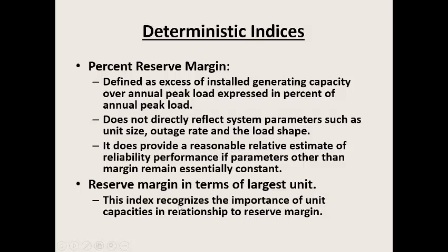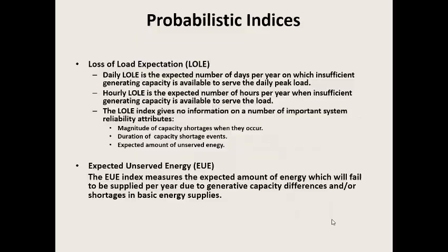This recognizes the importance of the unit capacities in relationship to the reserve margin, because the units which have larger capacities, when they fail, are going to have a more dramatic effect on the reliability than the smaller units. Now, the probabilistic indices.